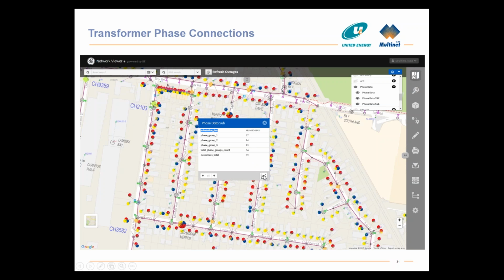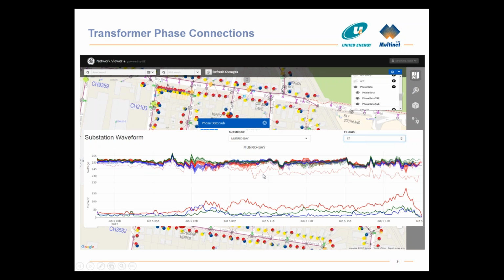From here we can drill through and look at the specific loads on that one. We don't have any measurements on the transformers themselves, but with all the smart meter data coming in, we can now plot each customer's voltage on that transformer and see what their voltages look like. Here we can see one that is potentially incorrectly mapped to that transformer - it just does not look like the rest.